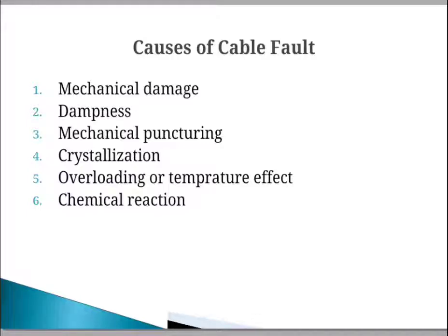Then the second one is dampness. When the level of water is just near the cable laid in the ground, then dampness of the paper insulation in the cable occurs, which may damage the sheath. It means the insulation property of the cable goes on reducing because of the water, and a fault will occur.